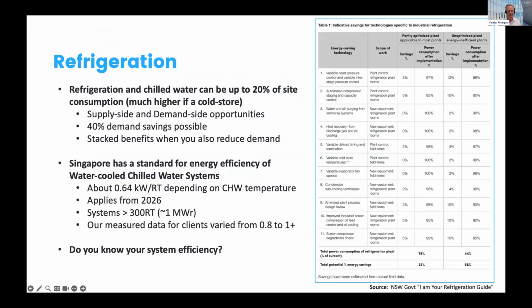All right. Okay, so jumping over to refrigeration. Now, refrigeration has a lot of similar opportunities because you have several compressors in a system and you're looking to optimize overall system efficiency. Up to 40% demand savings are totally possible, and we've seen it. I saw it 20 years ago. There was one of the first really big VSDs went in on a brewery site to control the refrigeration compressor.